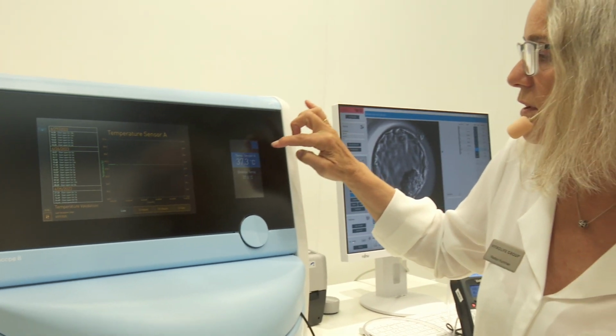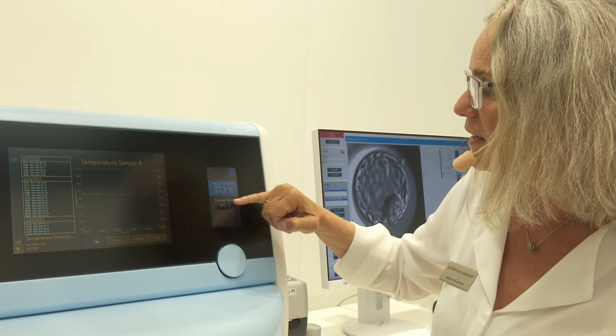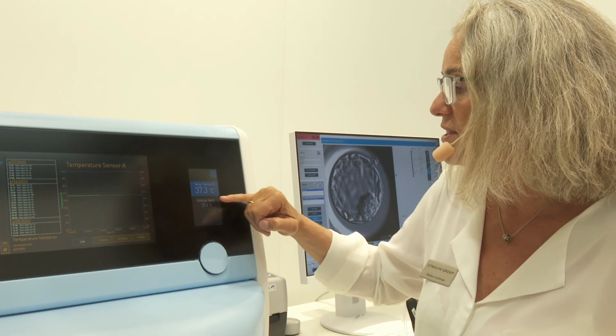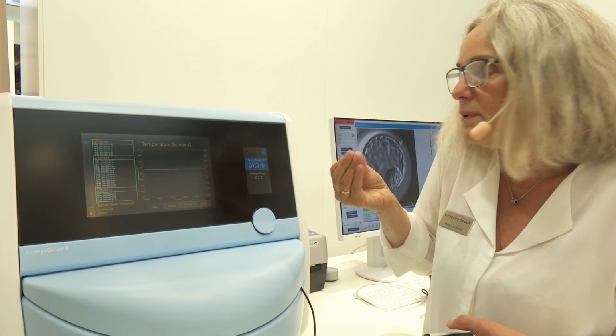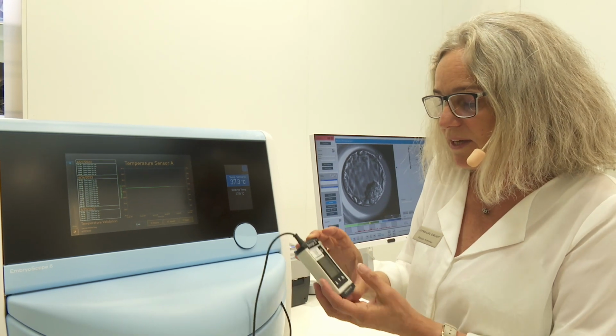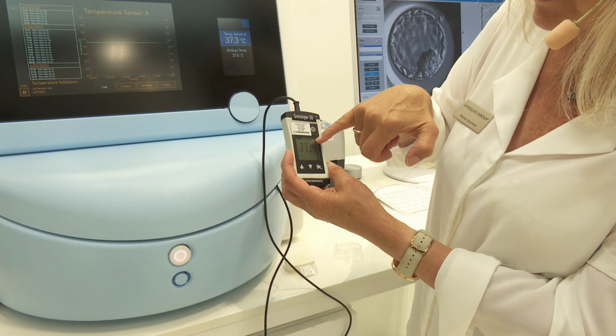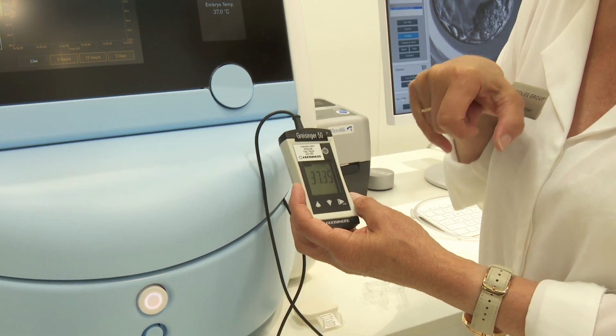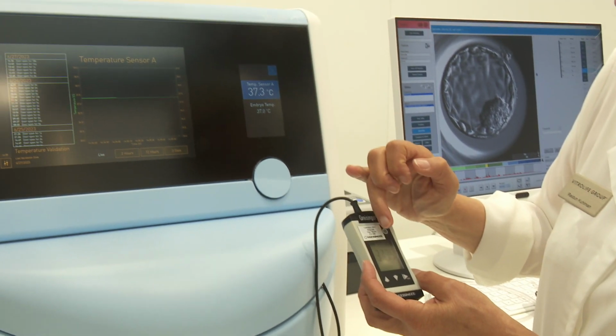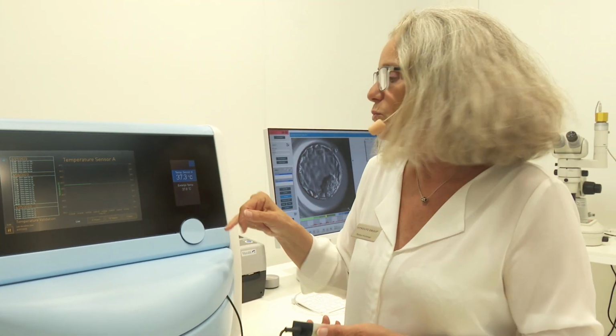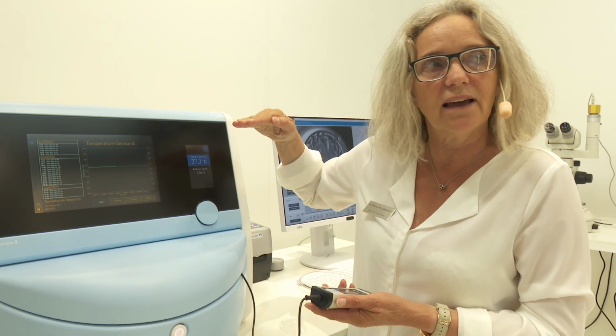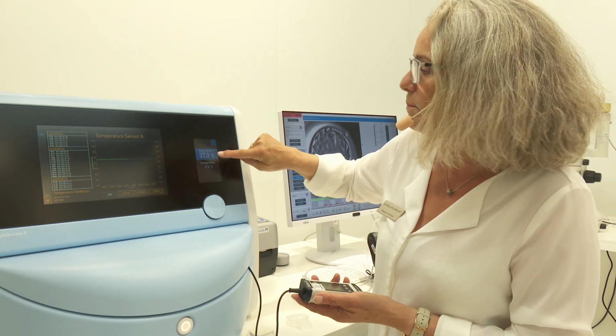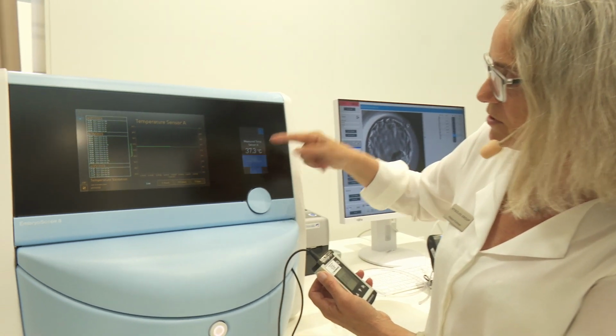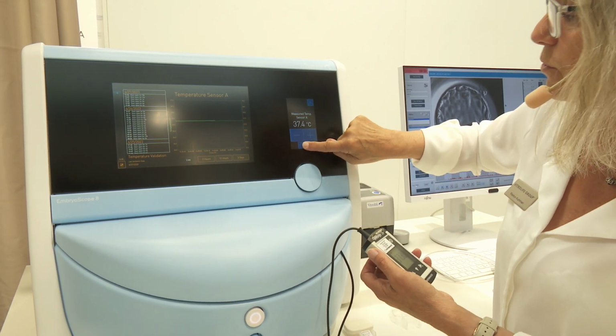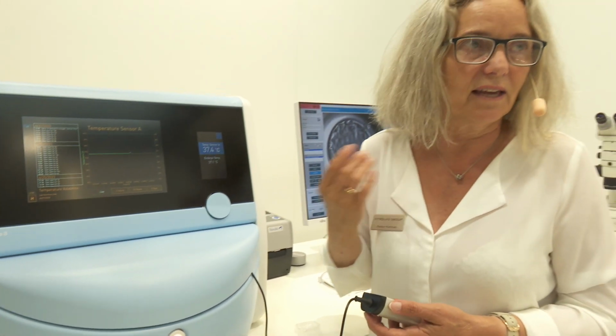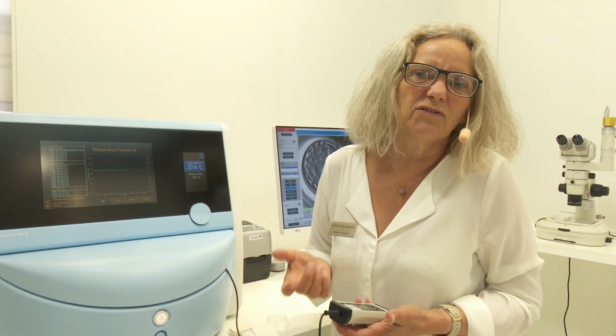When you look here at the screen where we measure, to ensure 37 in the medium where the embryos reside, it has to heat up to 37.3. So when I do my measurement, it will show 37.3 here, 37.3, 37.4, so it's really, really stable. But in case it was maybe 37.5, then you would tell the machine that it's a little bit higher than expected, so you want to calibrate a little bit down. And then you'd enter here that it actually was maybe 37.4, and you press confirm, and then it will start calibrating, and you will do a new measurement 15 minutes later, I would say.